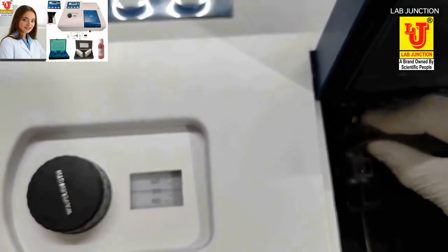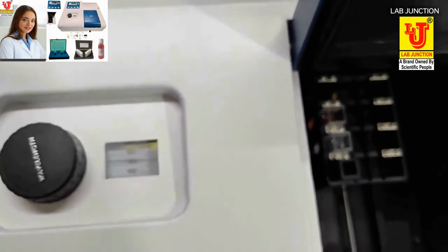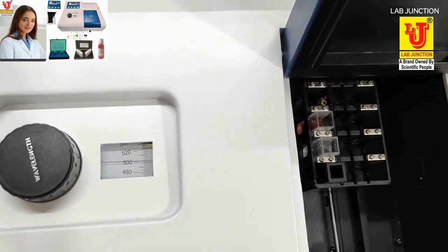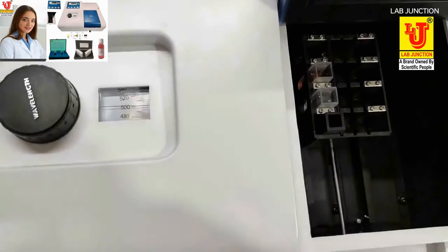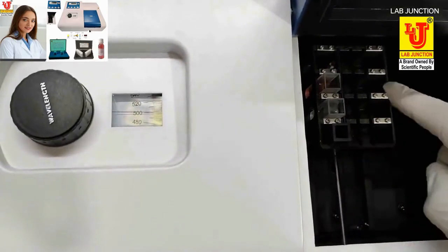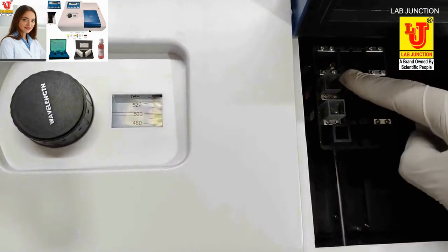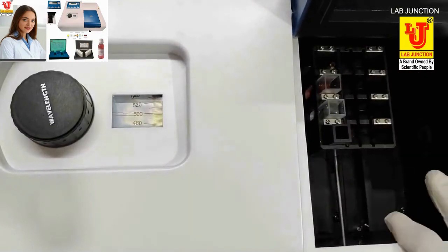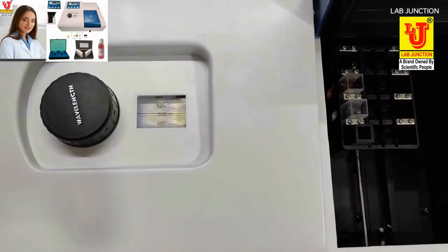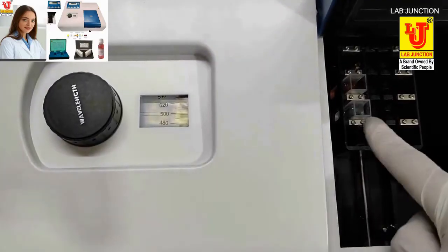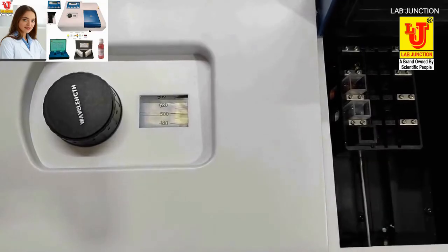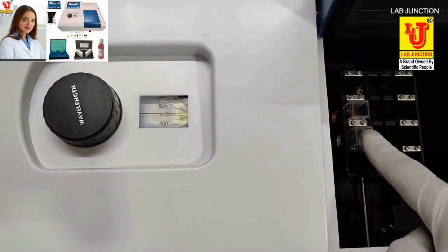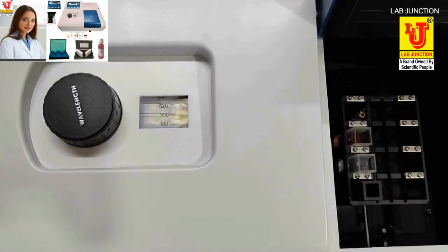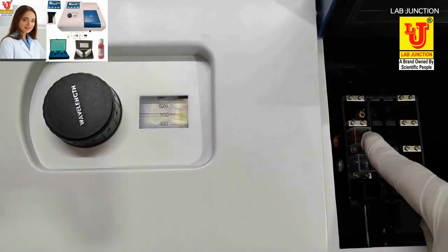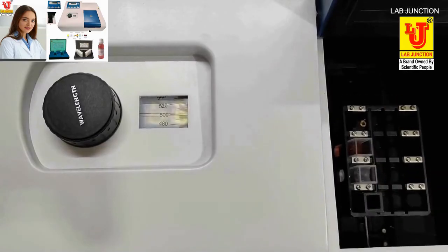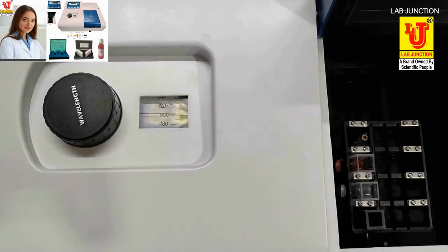Another position I am placing the sample this way. First is on dummy, second is on blank, third is on sample. Now this is position 1. Position 1 on dummy. Now position 2. On position 2, blank cuvette is there. Position 3, sample cuvette is there. Position 4, again sample cuvette is there.